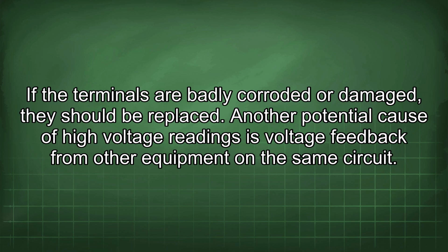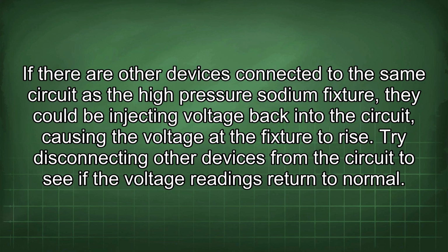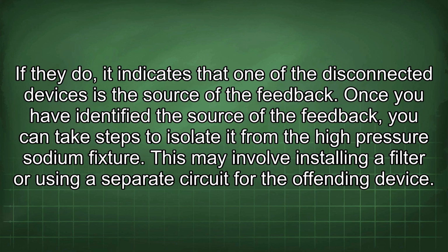Another potential cause of high voltage readings is voltage feedback from other equipment on the same circuit. If there are other devices connected to the same circuit as the high-pressure sodium fixture, they could be injecting voltage back into the circuit, causing the voltage at the fixture to rise. Try disconnecting other devices from the circuit to see if the voltage readings return to normal. If they do, it indicates that one of the disconnected devices is the source of the feedback. Once you have identified the source of the feedback, you can take steps to isolate it from the high-pressure sodium fixture. This may involve installing a filter or using a separate circuit for the offending device.